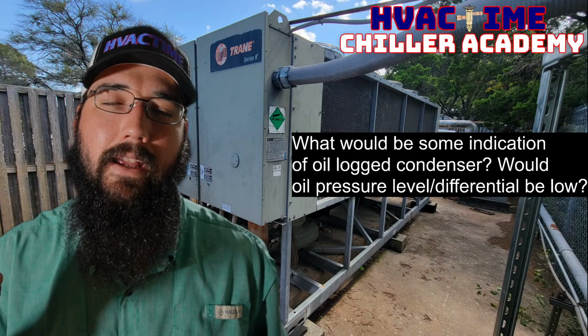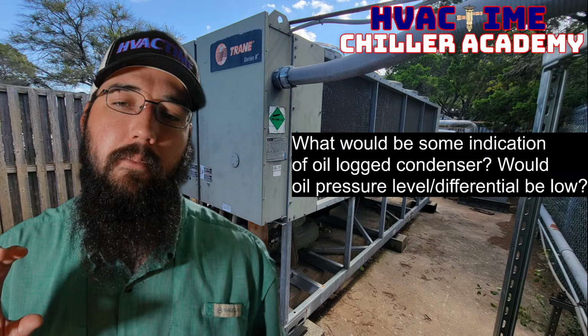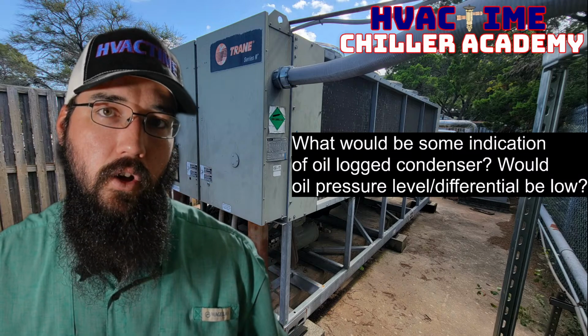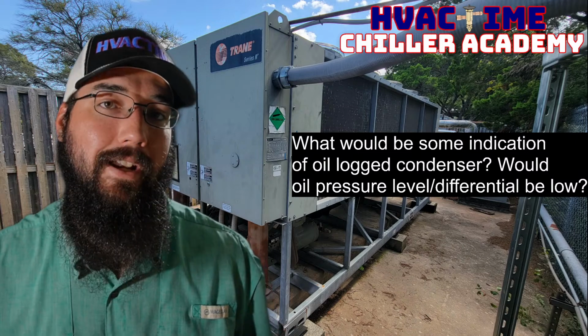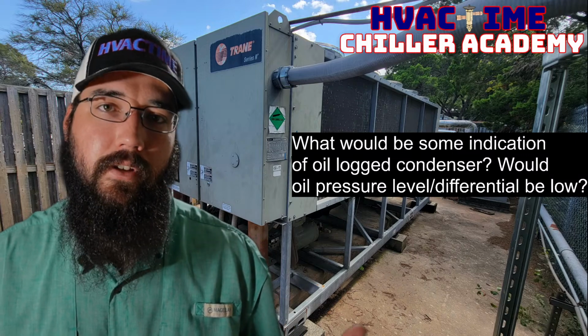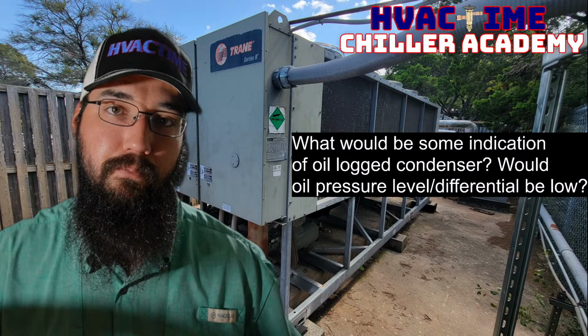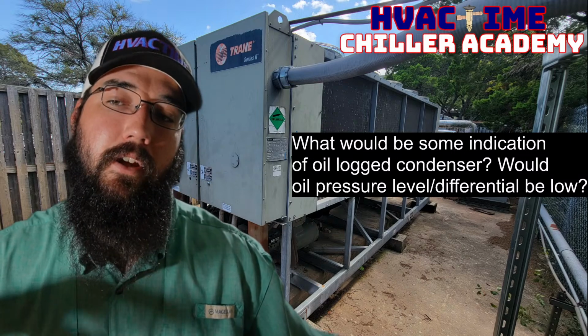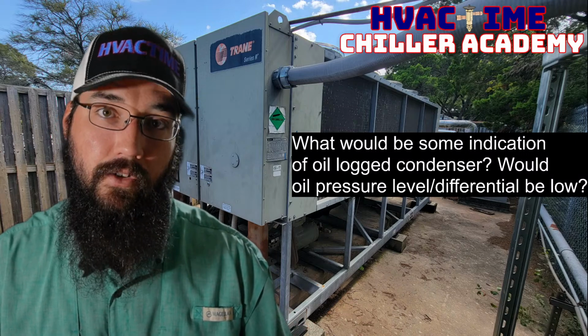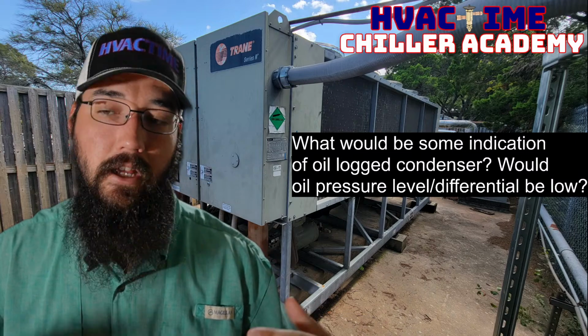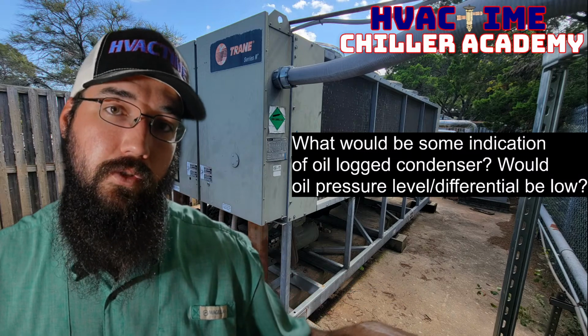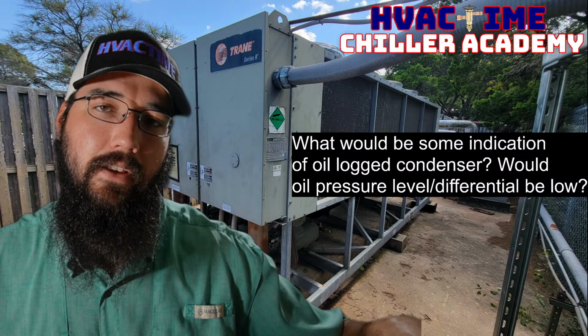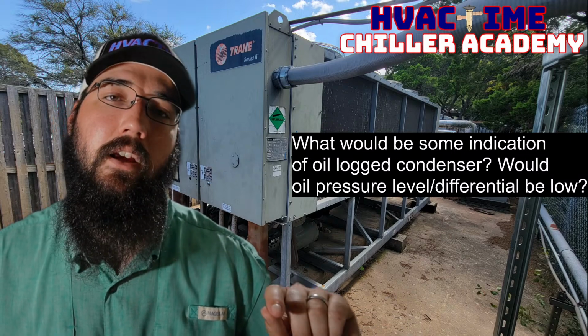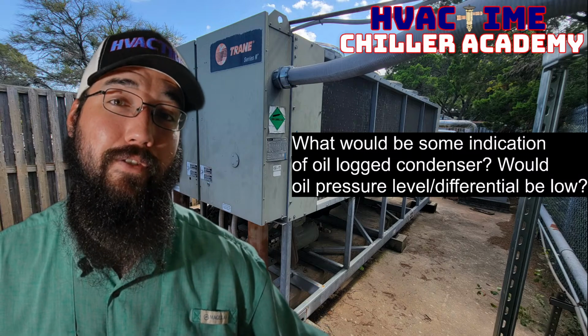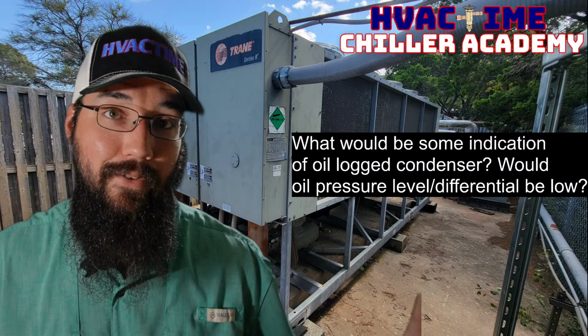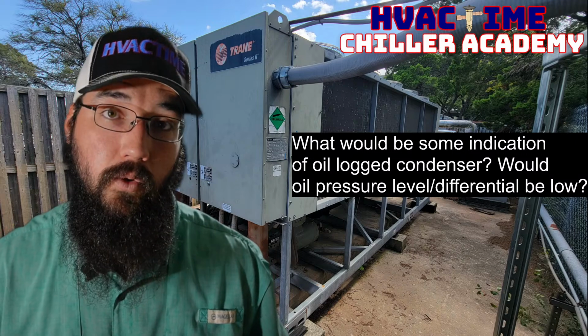What I have not seen is it affecting directly the oil pressure or differential. Those aren't going to be low in terms of something like that. If anything, they might start running high. But what it will do is affect your heat exchange and your saturation temperatures on both your evap and your condenser. Because if you've got a heavy enough oil charge that you're coating the condenser that severely to cause head pressure to elevate because of oil specifically, not because of other factors, then that also means you're heavily stacking oil in your evaporator, and that's going to cause your evaporator to also run very poorly. So in my experience, I will usually see the symptoms in the evaporator first, and eventually, if it's bad enough, you will start to see those same symptoms on the condenser side.